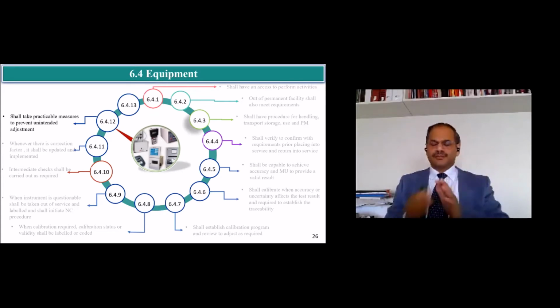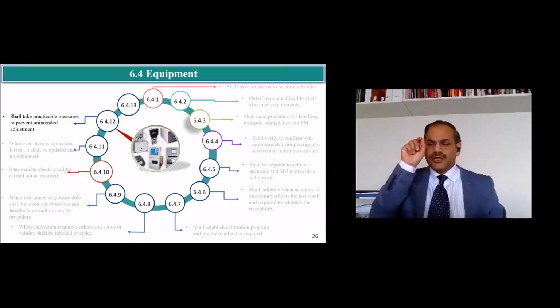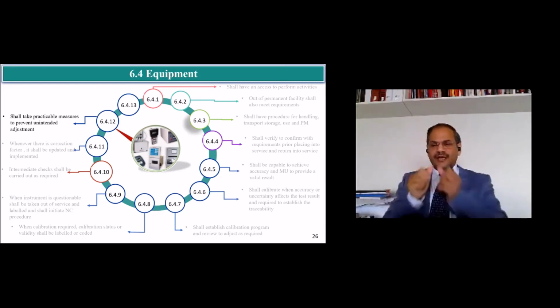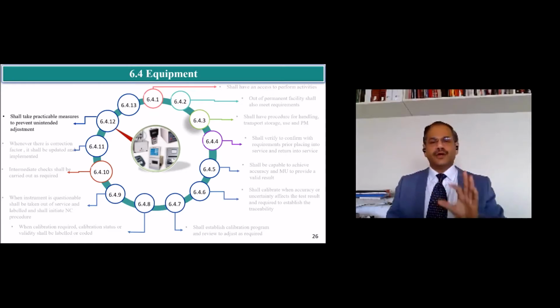For example, you have a simple instrument like a dew point meter. There is a small hole through which you can change the setting. So when you calibrate, put a label on that and sign it. If someone has tampered with it, it means it was unintentionally handled. Those are the practical ways you have to do it.